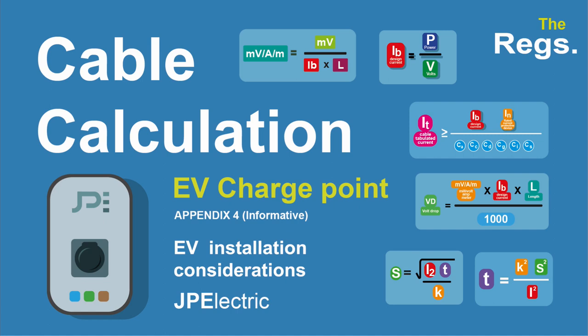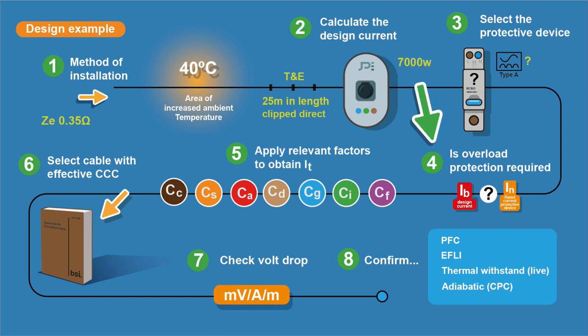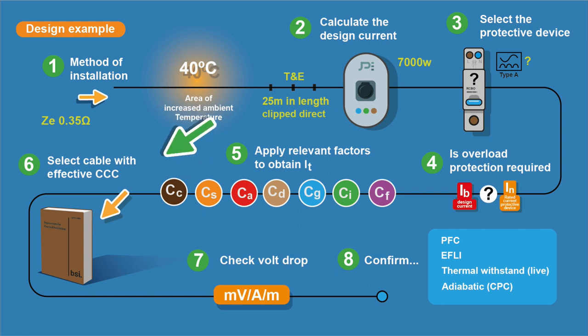Let's do a cable calculation for an EV charge point. The basics are relevant for any circuit and I'll also try to point out some considerations when you're installing an EV point — they're not that straightforward. Here's an overview: method of installation, cable choice, how it's getting installed in the building, then we calculate the design current, select the protective device, consider if overload protection is required, apply correction factors, select our final cable, check our volt drop, then confirm our cable choice is suitable for the load.